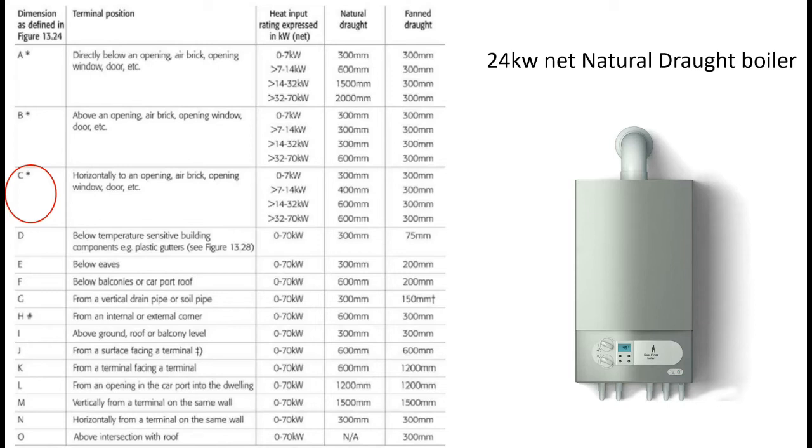So what we need to do now is identify the size. So it's between 14 and 32 kilowatts. We know it's natural draft. And we simply match these two up together, see where they meet. And it's at 600 millimeters. So the measurement C on the previous drawing, when you're using a 24 kilowatt natural draft boiler would be 600 millimeters minimum distance away from the window.